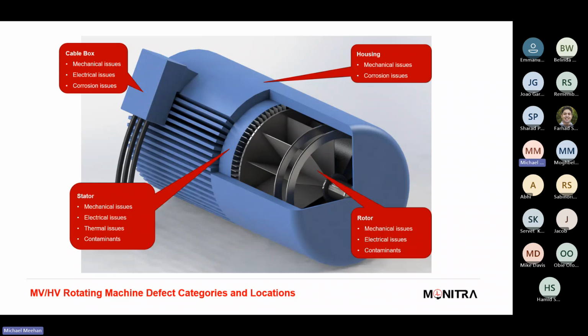The housing itself, obviously, it's important to keep the motor housing free from moisture, free from contamination, make sure all the seals are healthy. If the housing seals become compromised and all of a sudden you get dust, steam, other contaminants in and around the winding, obviously over time that contamination on the winding becomes a problem, and the winding itself will start to track, which will then start to create failure modes on the winding. And you can pick this up in PD activity, the surface tracking PD patterns, which will correlate to contaminated windings. And there's a mining operator right now actually using data that were provided on contaminated winding, and now taking actions to do some dry ice cleaning and get that stator back to a more healthy state.